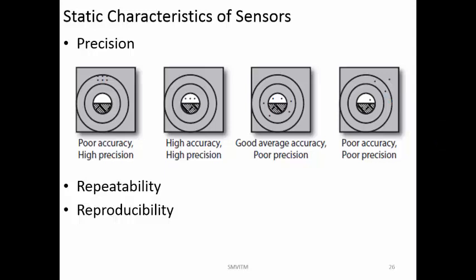That is precision. So precision is a combination of accuracy as well as repeatability. There is also something called reproducibility. Repeatability means you measure the same reading again and again and see how much variation there is. That is repeatability. Now what is reproducibility? Reproducibility is the characteristic obtained by taking the same measurement at different points of time. In repeatability, you use the same operator, same instrument, same location, same environmental conditions, everything the same. Only you take n number of readings.